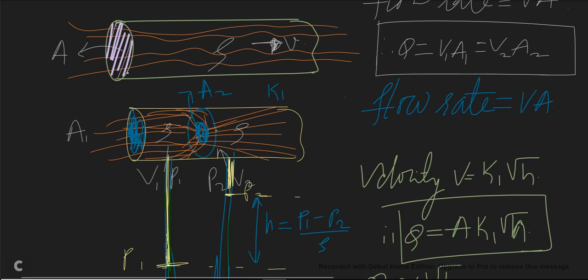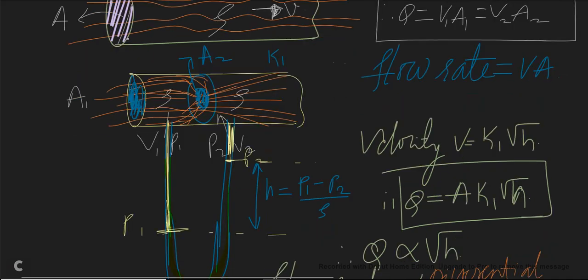On the upstream side, there is a very low velocity and fluid continuously accumulates, causing very high pressure on the walls. The velocity at this side is V1 and the pressure is P1, where pressure is higher and velocity is lower. On the downstream side of the orifice plate, the fluid content is smaller near the plate, so the pressure is lower — let us say P2 — and the velocity is very high, V2. The opening has a cross-sectional area of A2, while the pipe side has pressure P1, which is higher compared to P2.